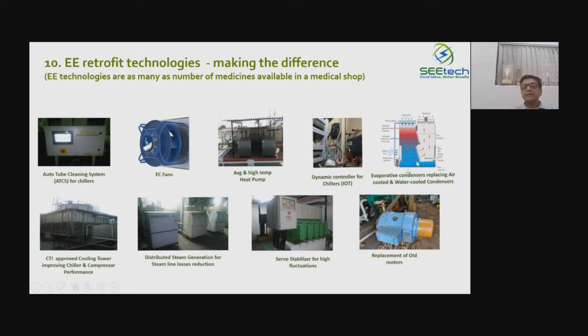This is an evaporative condenser, one of the case studies we saw earlier. Even in water cooled chillers, evaporative condensers have given savings. But these are not generic - I don't mean you should change everything in the house. Every feasibility has to be evolved for every single case because something is always different. Then a cooling tower institute approved cooling tower definitely makes a significant difference.